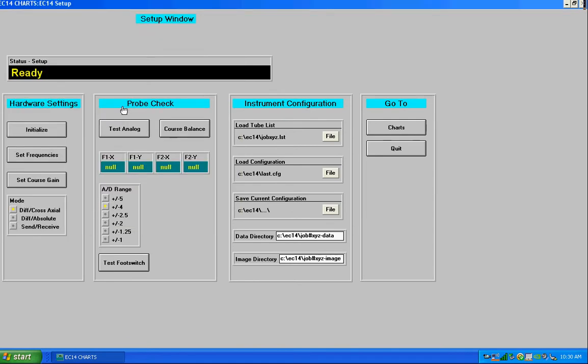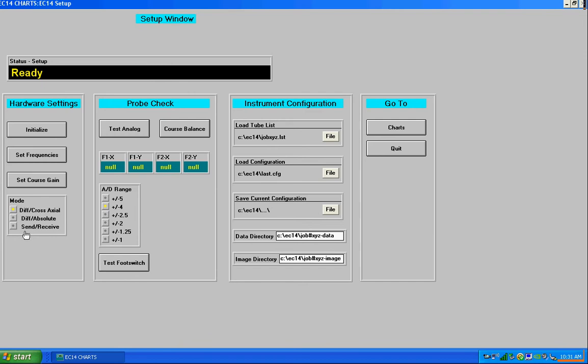And then this is the bridge configuration mode. Right now it's set to differential cross-axial type probe. You could also set it for a differential absolute probe which does simultaneous injection into one of the probe coils so that you can get an absolute test. And then also we support a send receive mode.